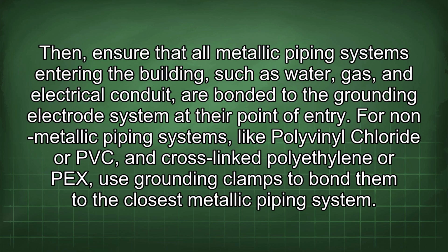Then ensure that all metallic piping systems entering the building, such as water, gas, and electrical conduit, are bonded to the grounding electrode system at the point of entry. For non-metallic piping systems, like polyvinyl chloride or PVC, and cross-linked polyethylene or PEX, use grounding clamps to bond them to the closest metallic piping system.